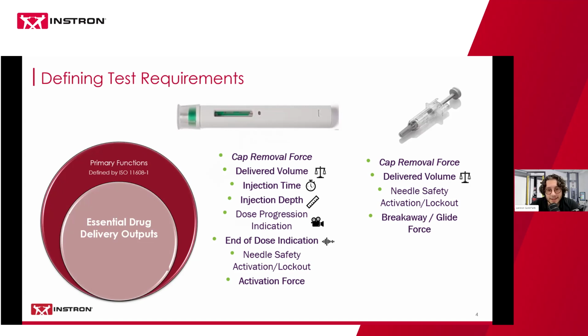And I've put icons just to highlight that these are not all force measurements. A lot of them are using some other measurement transducer, whether it's a scale or a vision system or a camera or a microphone. We have to integrate additional devices into a system to be able to fully evaluate these kinds of devices. And then, looking comparatively to a prefilled syringe, there's so many additional requirements for what is required to test. On a prefilled syringe, you would only be interested in the delivered volume piece that requires additional transducers for a system. Everything else is standard force related testing. So this really highlights that shift and that gap in requirements between prefilled syringes and auto injectors.